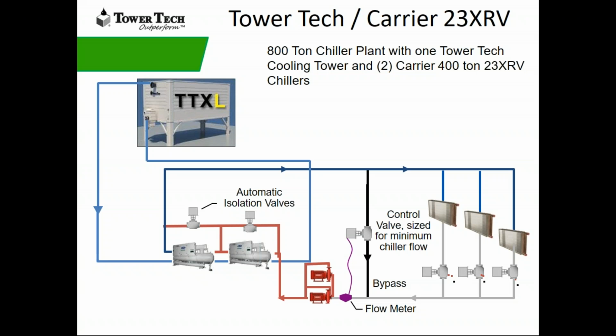So this is the analysis we're going to do. We're going to look at a TowerTech cooling tower, and we're going to match it up with a Carrier 23XRV system, and we're going to look at an 800-ton chiller plant with one TowerTech tower. Okay, and we're going to use 2 Carrier 400-ton 23XRV chillers. So the design that we like to do in this market, when it can be done with a 2 chiller plant, is we like to operate 2 chillers with a single tower. Most of the time you're operating those chillers, 1 chiller is operating at a time.